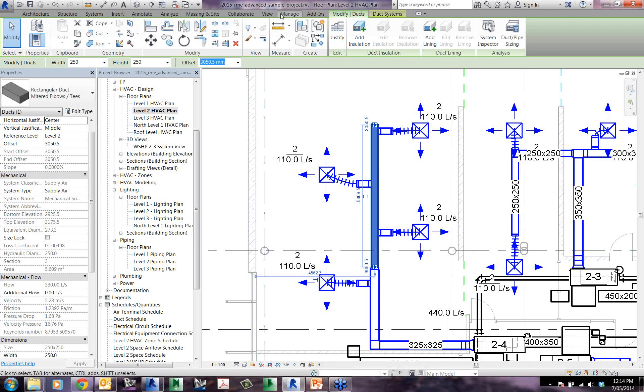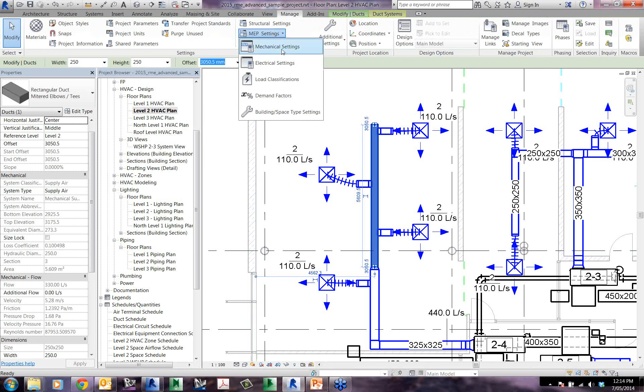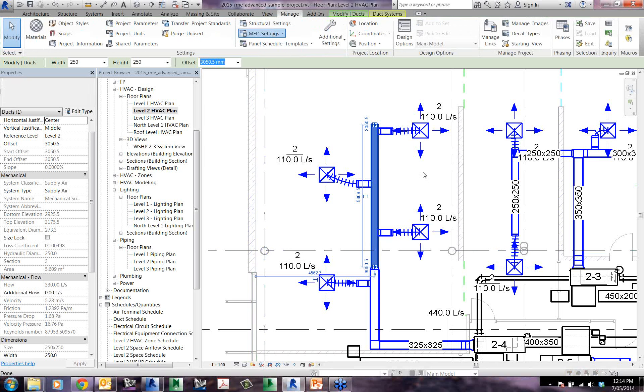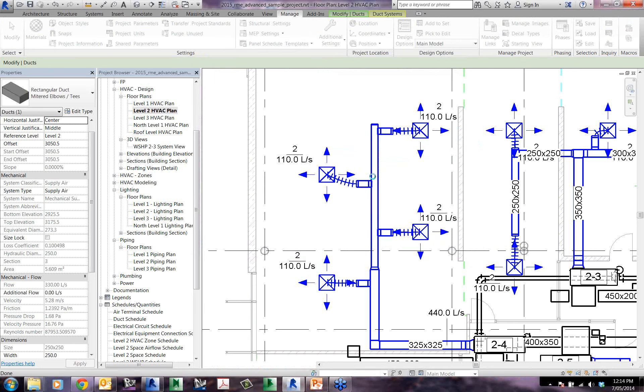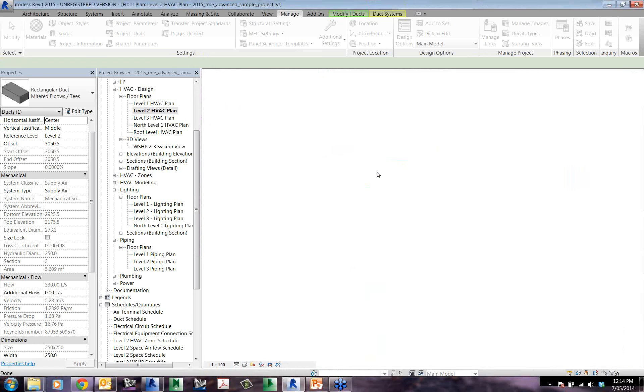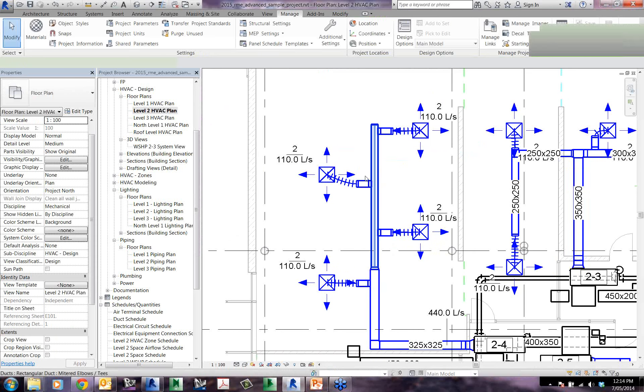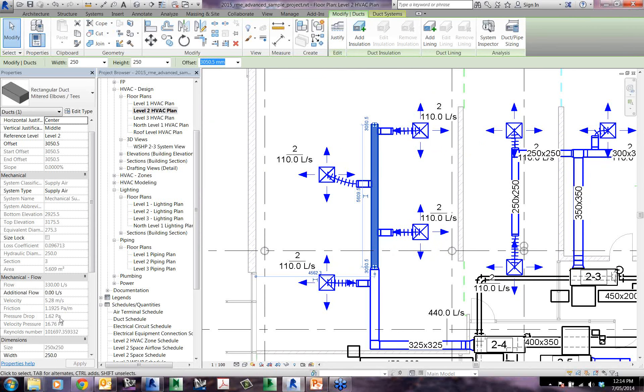If we go back in and change it to the Haaland equation and click OK, we can see the same section of duct now shows a pressure drop of 1.62. So there are subtle differences in the way that it is calculating the pressure drop depending on which equation is chosen.